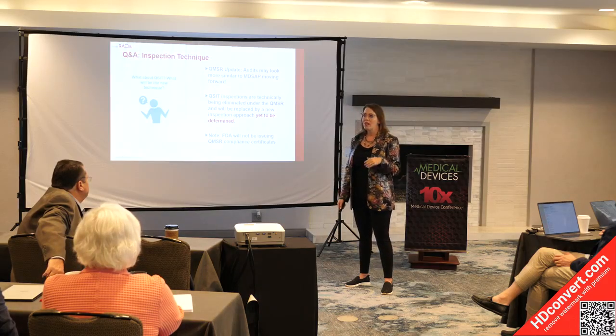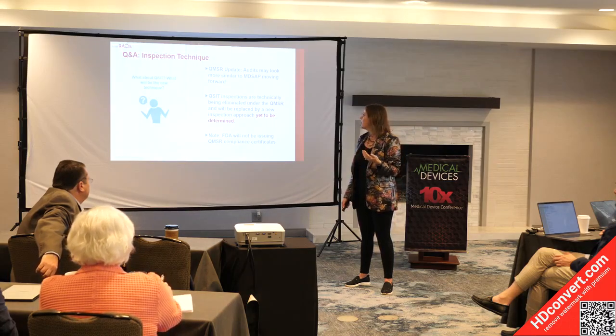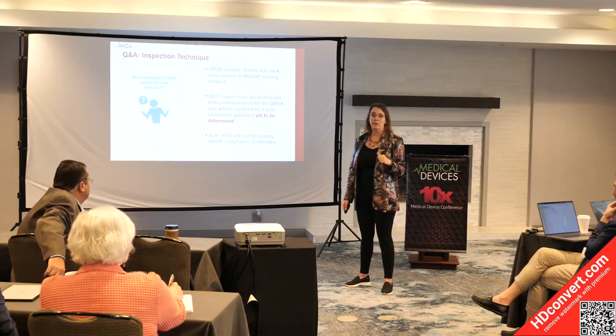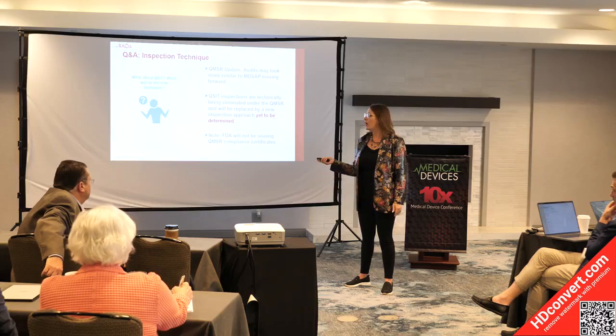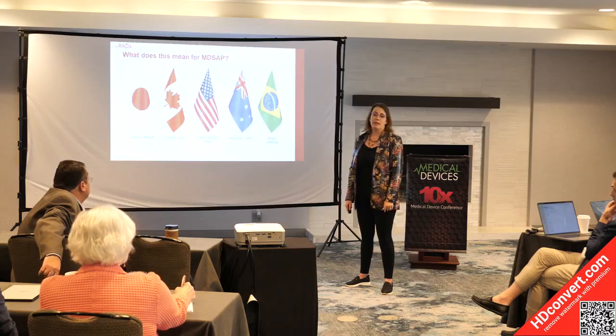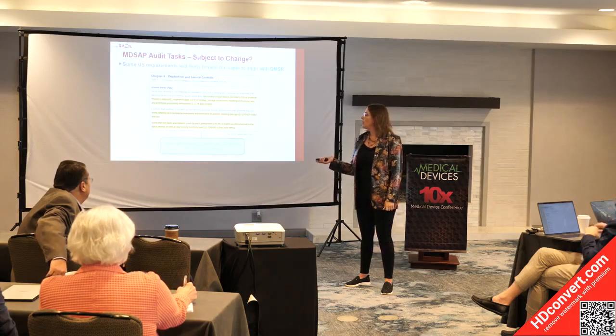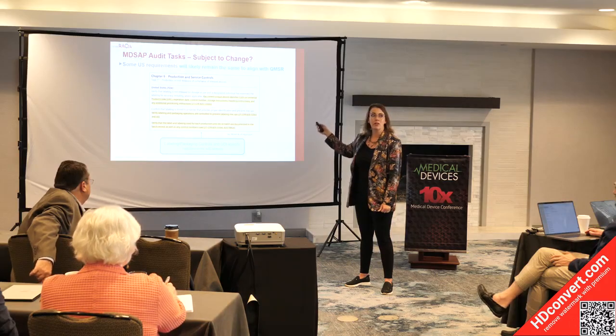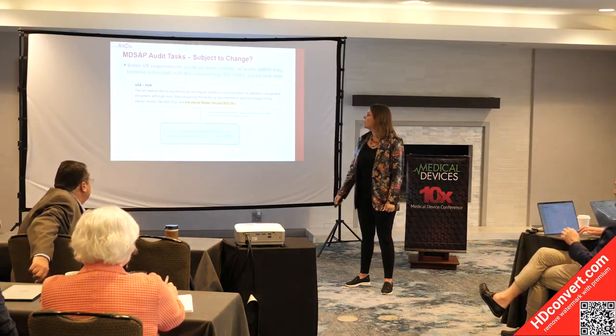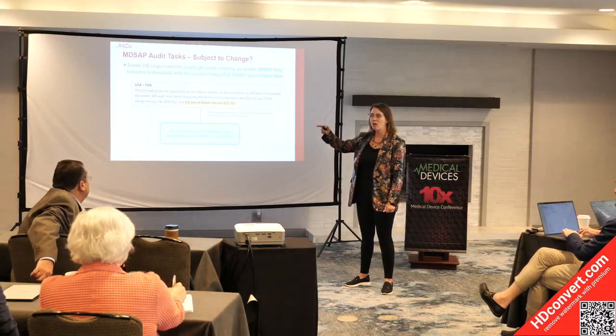The Quality System Inspection Technique (QSIT) is going to go away entirely — it's built around the QSR. FDA has not yet published what the new inspection technique will be, but it's very likely going to be MDSAP directly or MDSAP indirectly. For MDSAP itself, some tasks will stay the same where differences remain — like the UDI requirement — but some tasks will go away entirely where they have harmonized.